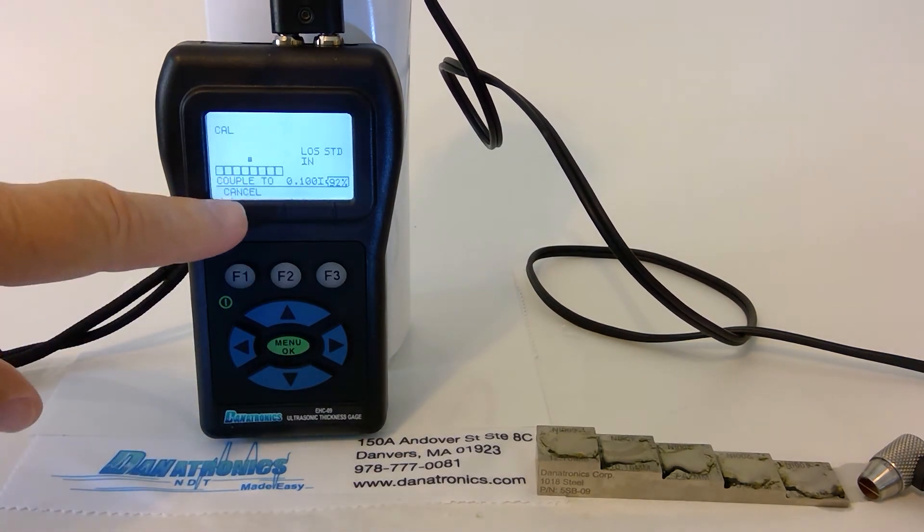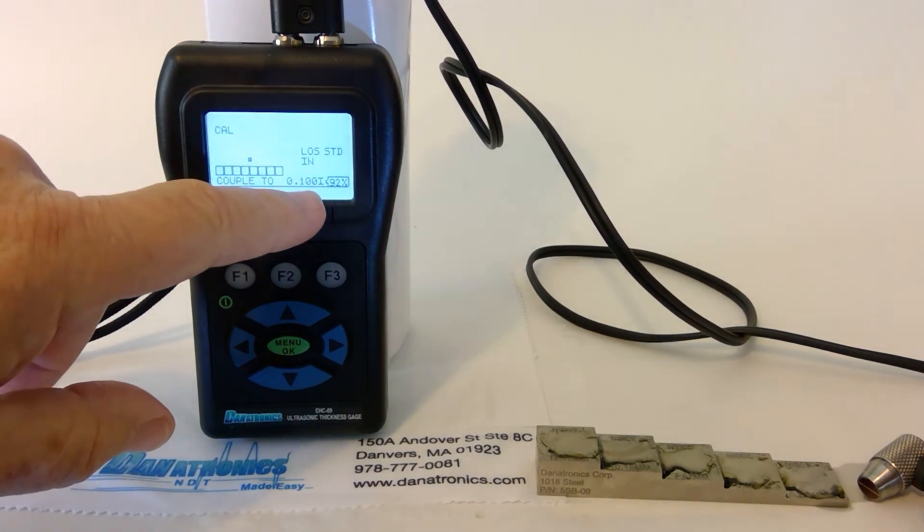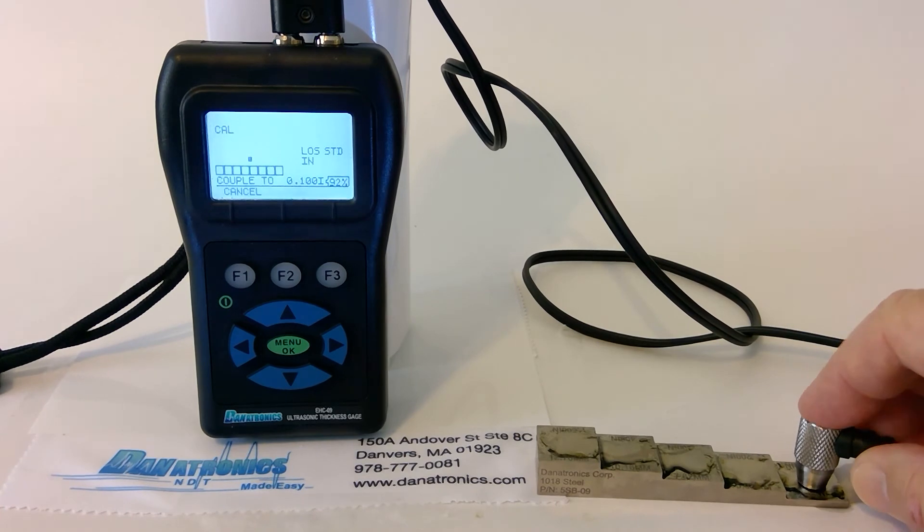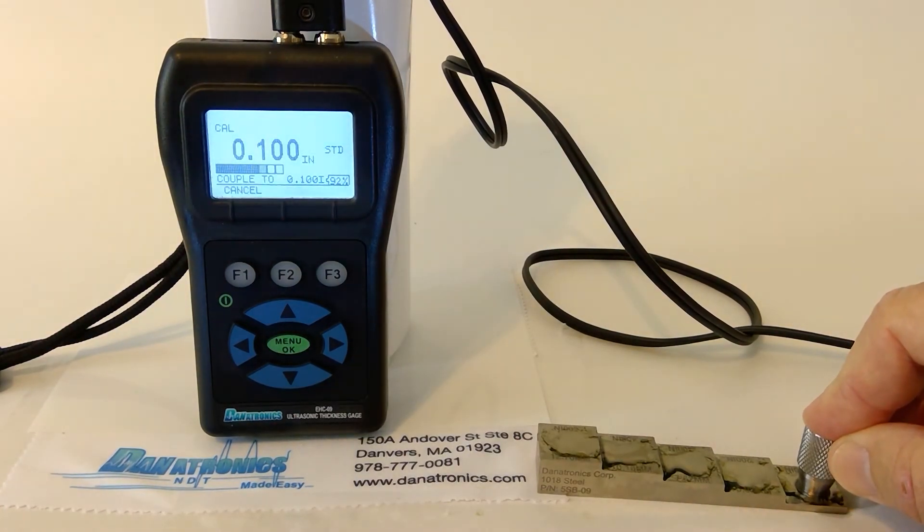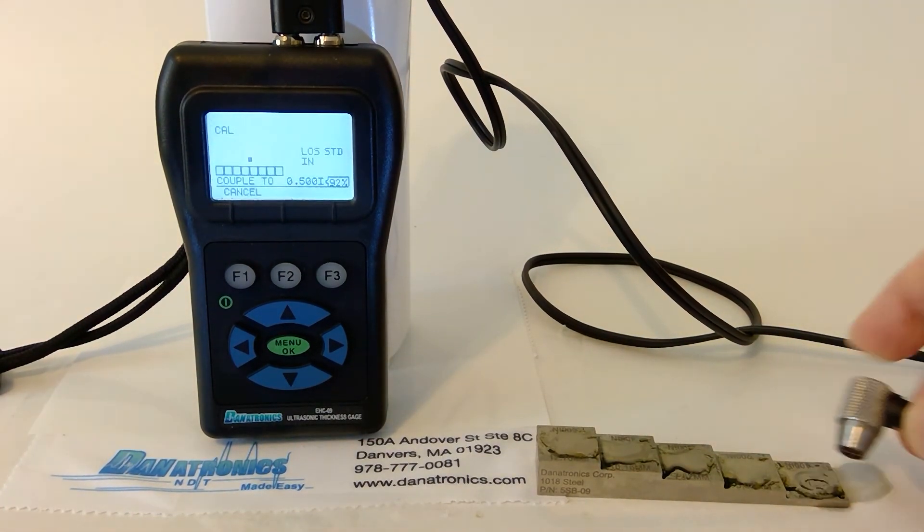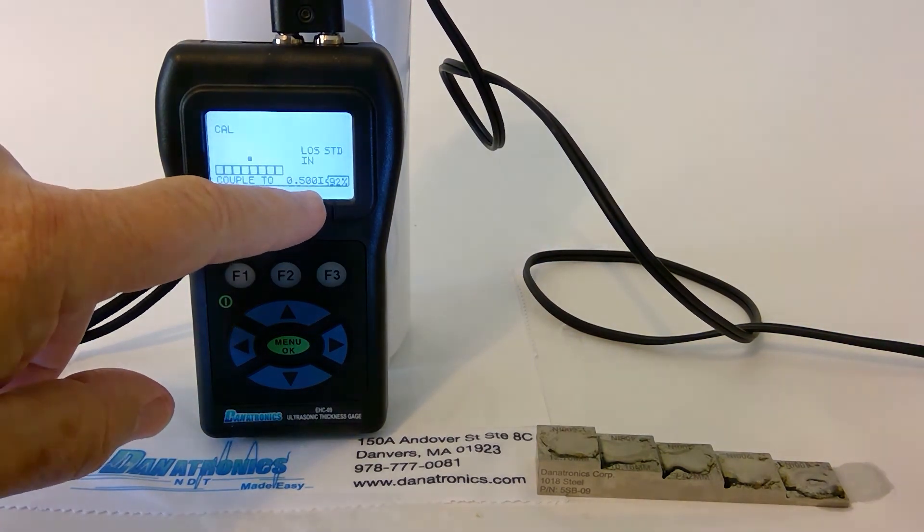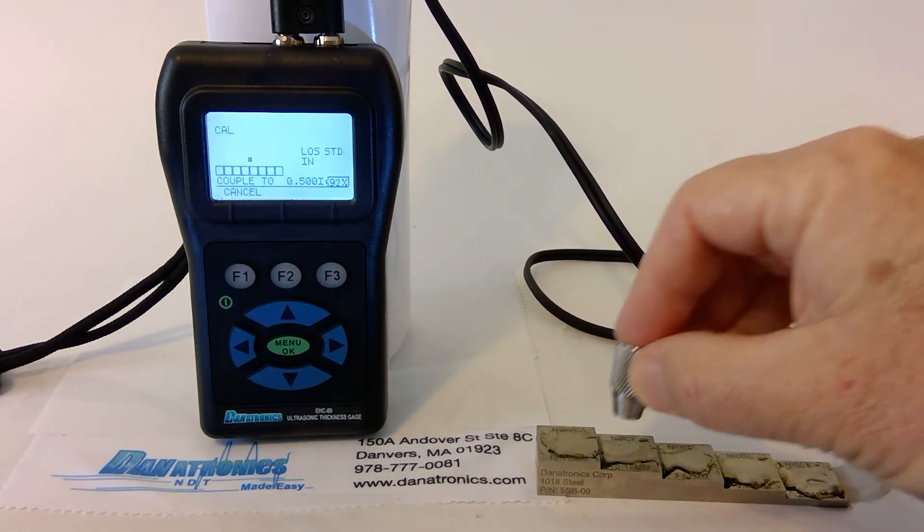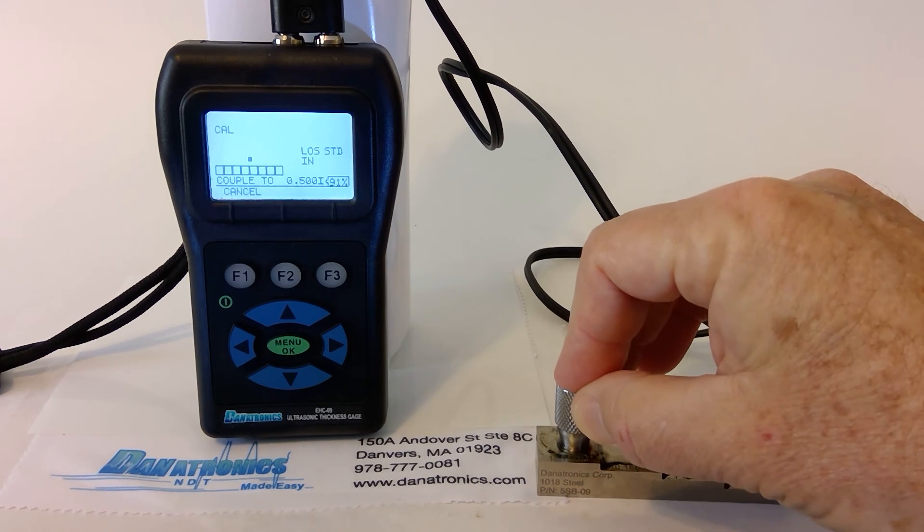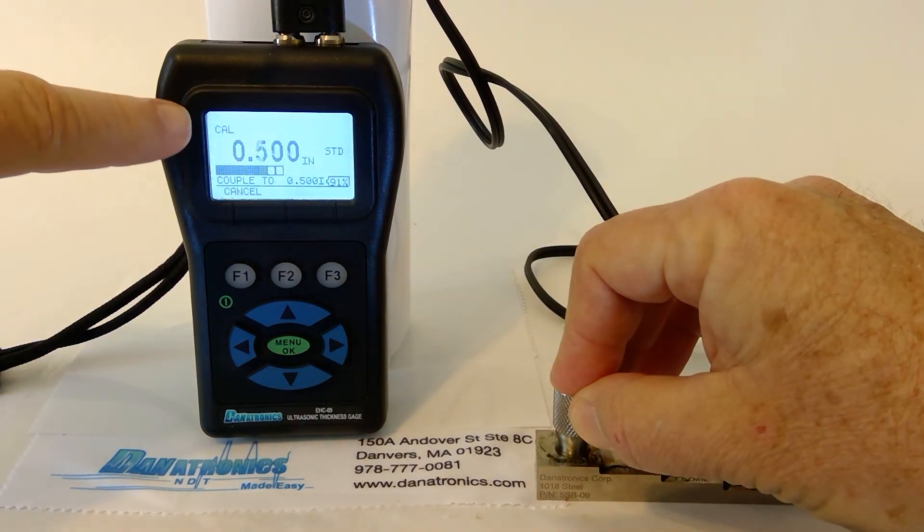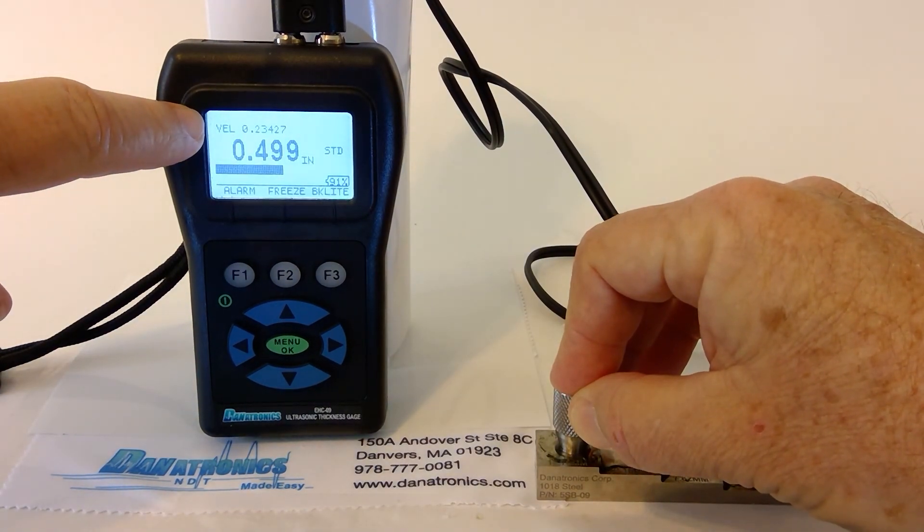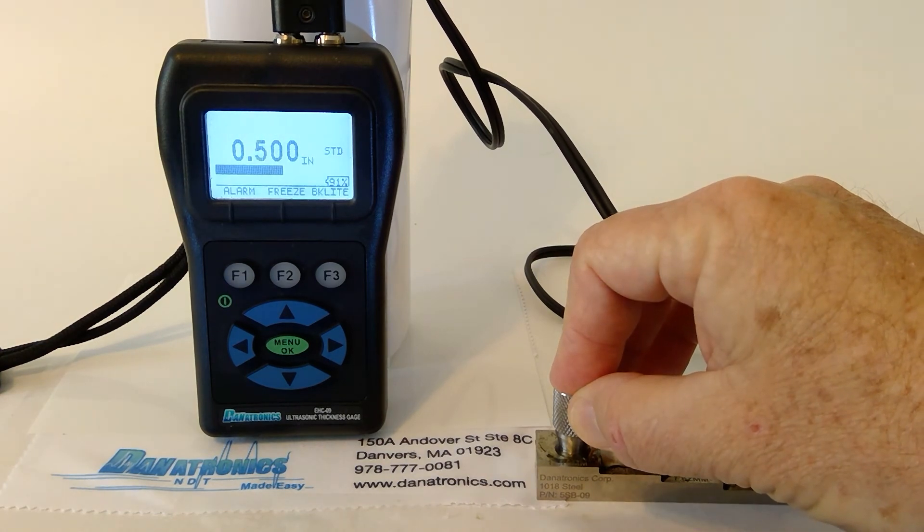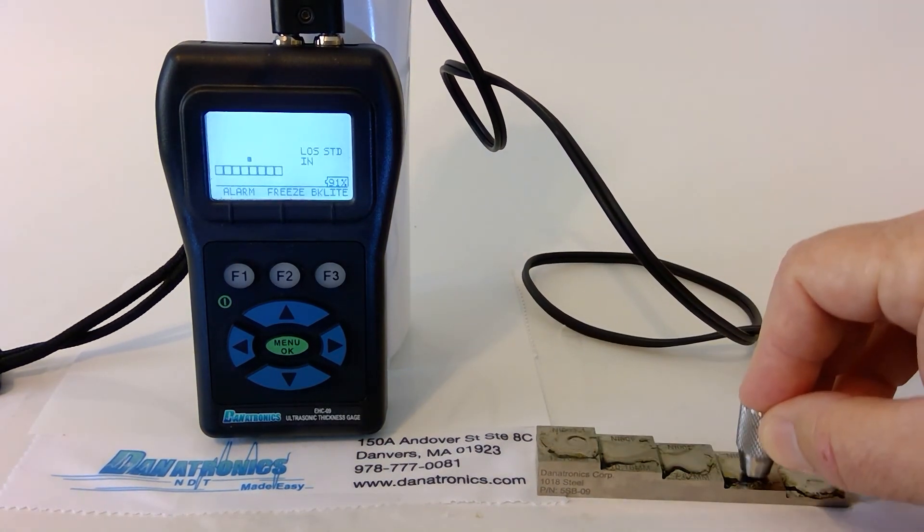Now it asks us to couple to the 100 thousandths side of the block. The gauge beeps. Now it's asking me to couple to the 500 thousandths side of the block. Once this is completed, you will notice at the top, it calculates the velocity. And now we are calibrated.